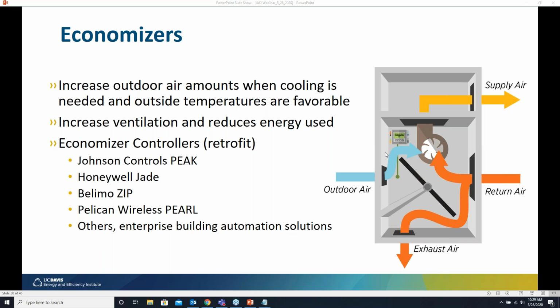So particularly in drier climates like the West and the North, economizers can increase ventilation and significantly reduce energy used. I just also wanted to point out that economizer controllers are often available as retrofit products. I listed a couple of examples here. This is one thing that I would consider looking at if you're considering some HVAC retrofits, is to add economizer controllers. And certainly if you have existing economizer controllers, make sure they're working because they're really going to be beneficial in this situation.